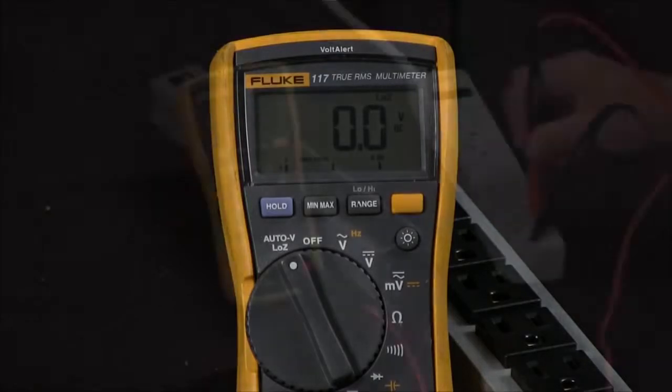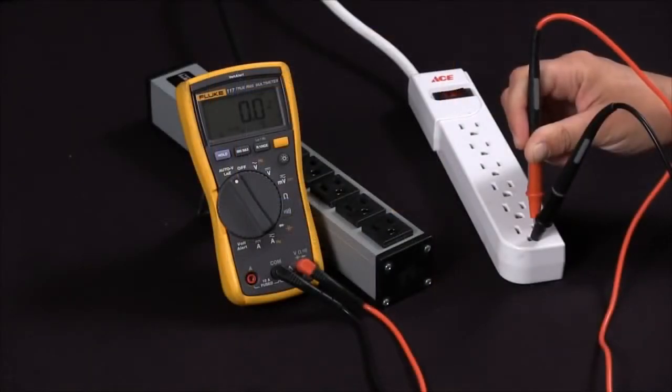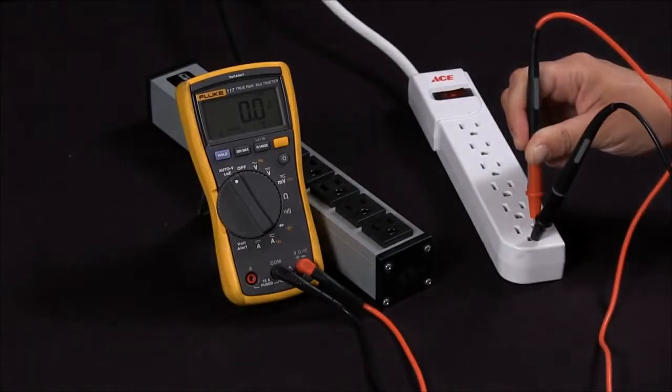So thus this is telling me that I am experiencing a ghost voltage from hot to ground and this is how to determine whether or not you're getting a true voltage or a ghost voltage with a Fluke 117.